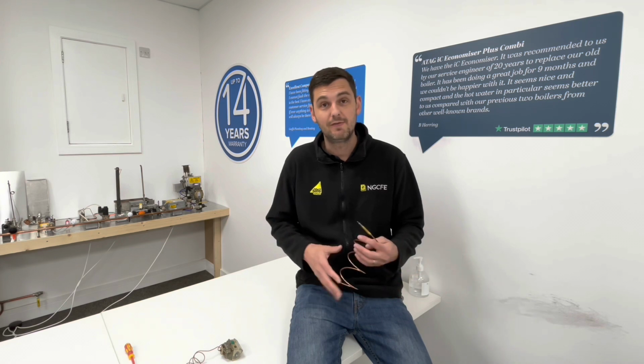So before we look at the controls board, it's really important that we understand some of the components associated with it. First of all, we're going to be working with many controls that operate using thermocouples, thermostats, and that kind of thing. We're also going to be looking at FSDs. Thermostats are there to basically maintain temperature via one method or another. FSDs are there to close the supply of gas if the flame's extinguished for any reason whatsoever.